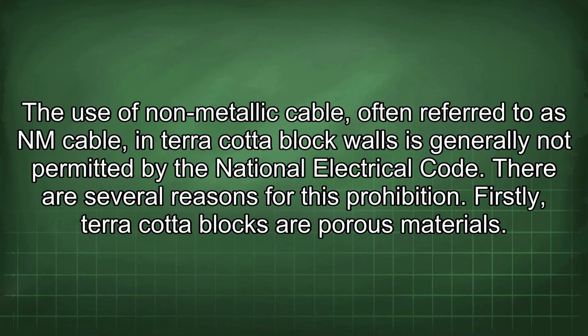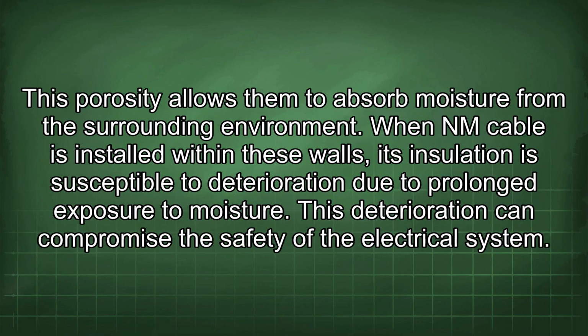The use of non-metallic cable, often referred to as NM cable, in terracotta block walls is generally not permitted by the National Electrical Code. There are several reasons for this prohibition. Firstly, terracotta blocks are porous materials. This porosity allows them to absorb moisture from the surrounding environment. When NM cable is installed within these walls, its insulation is susceptible to deterioration due to prolonged exposure to moisture. This deterioration can compromise the safety of the electrical system.